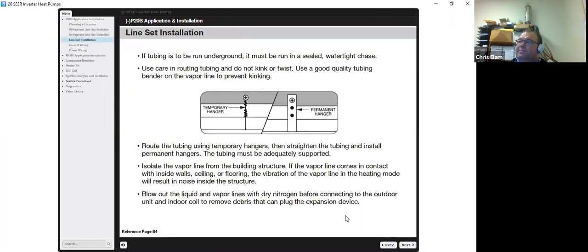Line set installation. If the tubing is to be run underground, it must be run in a sealed, watertight chase. Care should be used when you're routing your tubing. Do not kink or twist. Use a good quality tubing bender on the vapor line to prevent kinking. Route the tubing using temporary hangers, then straighten the tubing and install the permanent hangers. Do isolate the vapor line from the building structure. If the vapor line comes in contact with walls, ceilings, or flooring, the vibration of the vapor line in the heating mode will result in noise and vibration in the structure.